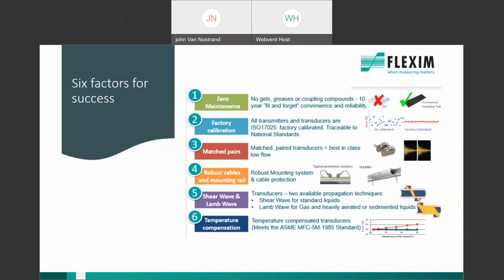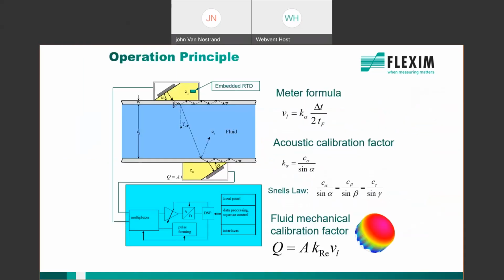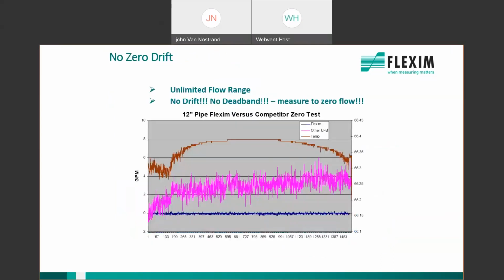I want to talk a little bit about that temperature compensation circuit. I like to show this because it illustrates the embedded RTD in the transducer block. As you see on the top of the slide, it says embedded RTD. This is not part of the measurement process. Rather, it's used to temperature compensate the transducer to account for any thermal effects that might be going on from the sun beating down on the transducers, for example. The American Society of Mechanical Engineers recognized the need for this compensation and wrote a standard called ASME MFC-5M, and FLEXIM is the only one that meets that prescribed recommendation.